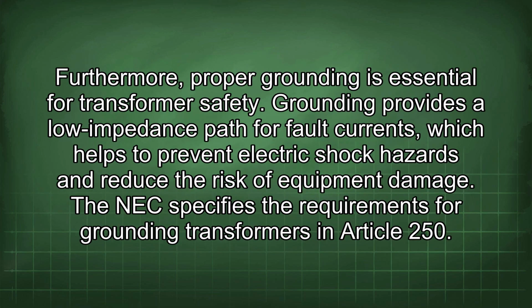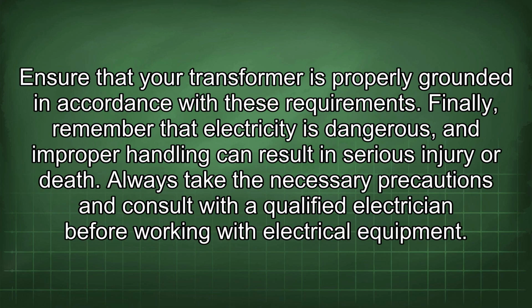Furthermore, proper grounding is essential for transformer safety. Grounding provides a low impedance path for fault currents, which helps to prevent electric shock hazards and reduce the risk of equipment damage. The NEC specifies the requirements for grounding transformers in Article 250. Ensure that your transformer is properly grounded in accordance with these requirements.